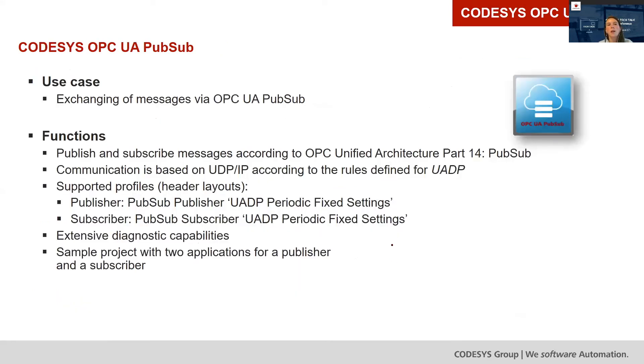What we provide with our library called OPC UA PubSub is the possibility to exchange messages via the OPC UA PubSub protocol between different controllers. You can publish and subscribe to messages according to OPC Unified Architecture Part 14, which defines the PubSub protocol. The communication is based on UDP/IP according to the rules defined by the OPC UA Foundation, named UADP.